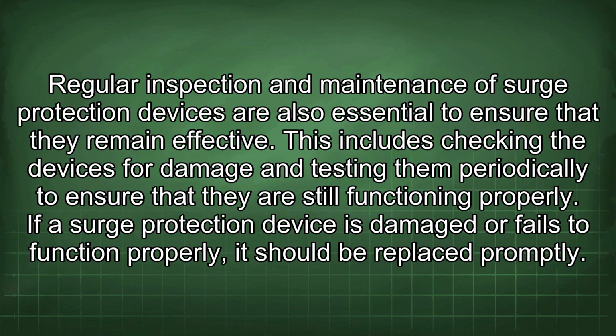Listed surge protection devices have been tested to meet certain safety standards and are more likely to provide effective surge protection. Regular inspection and maintenance of surge protection devices are also essential to ensure that they remain effective. This includes checking the devices for damage and testing them periodically to ensure that they are still functioning properly. If a surge protection device is damaged or fails to function properly, it should be replaced promptly.